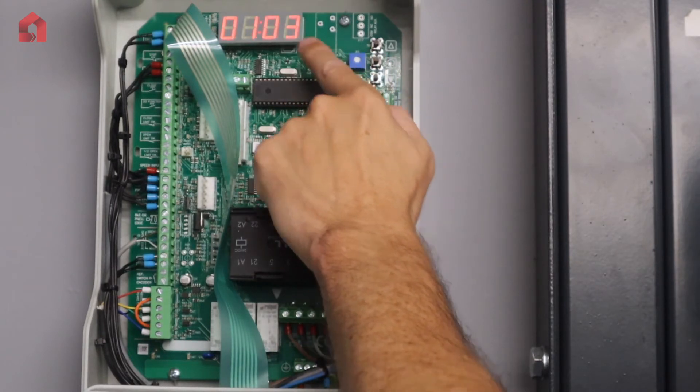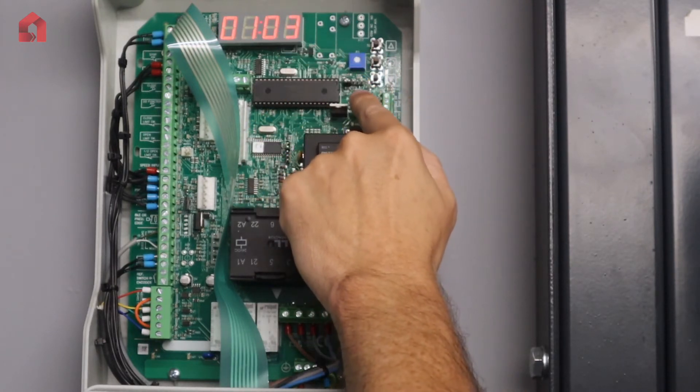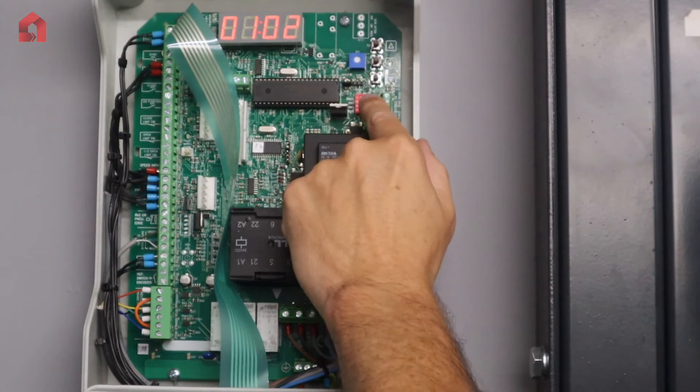press the middle stop, the right hand side display will flash. If I then change it to 02, that will make it impulse up dead man down. If I change it to 01, that will make it dead man both ways.